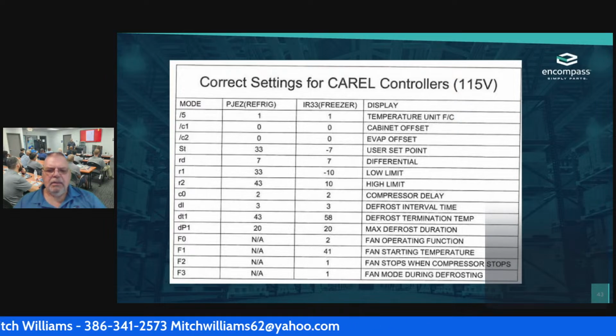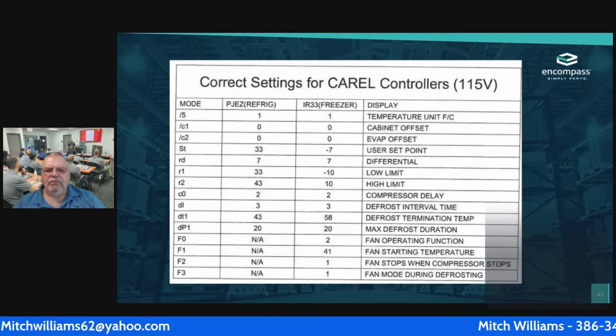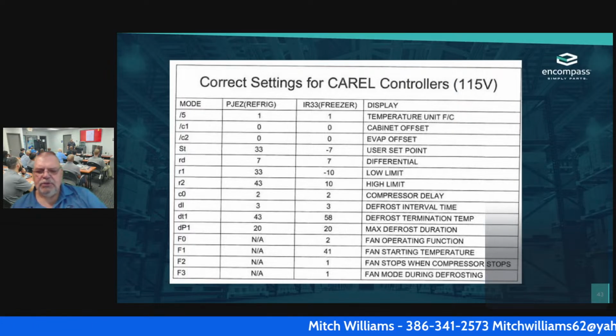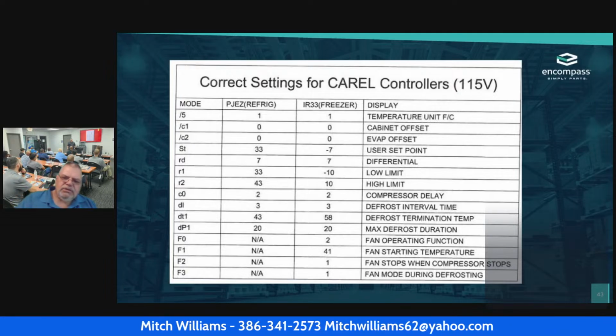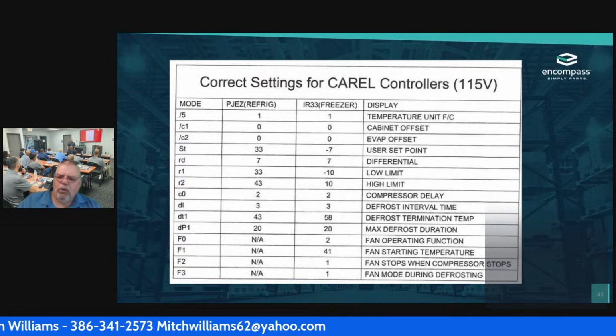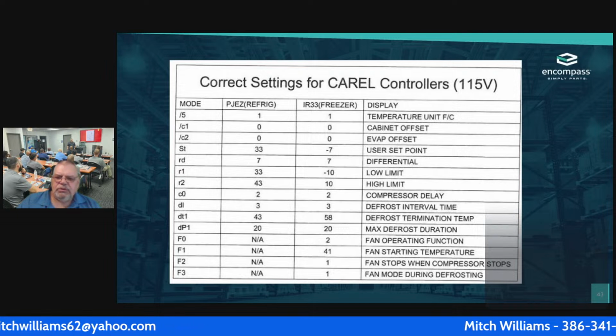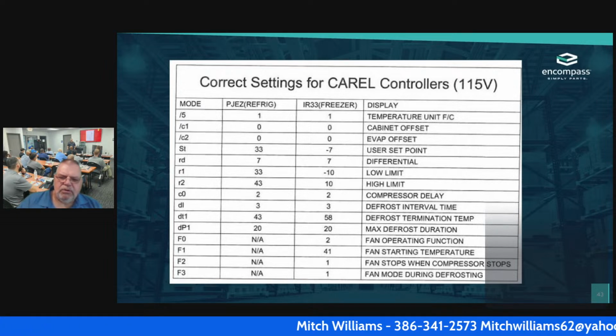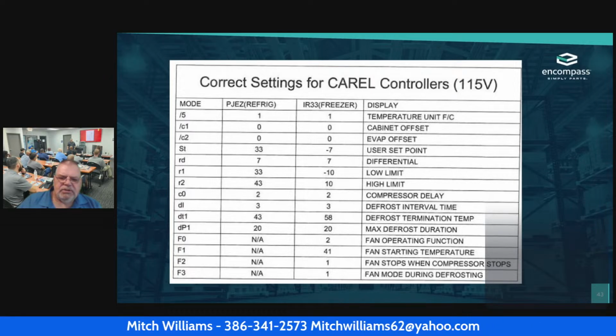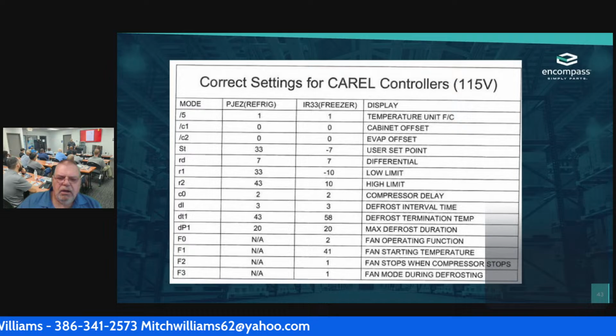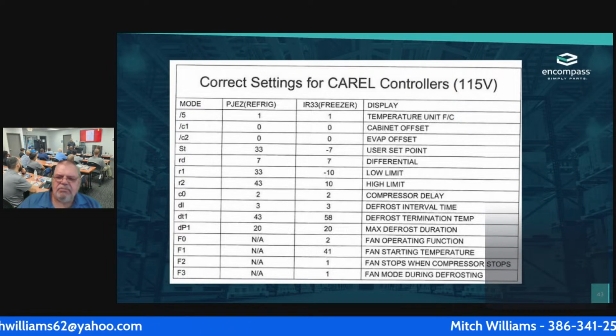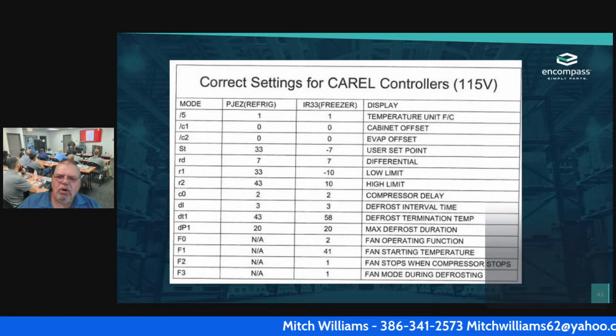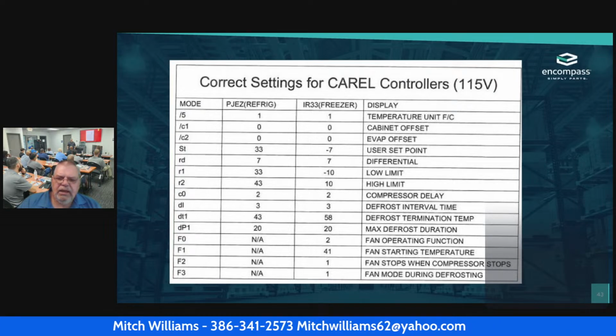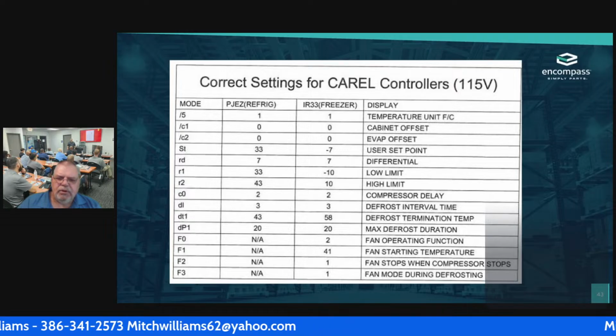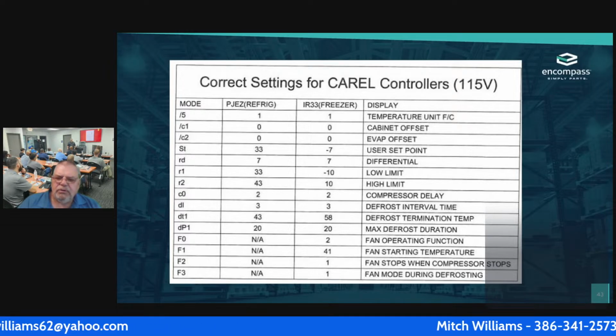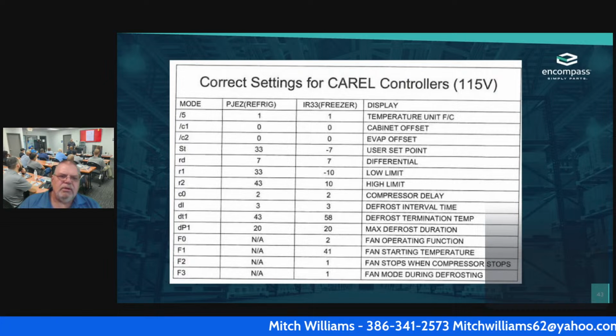That's the fan operating. Then F1, it's not applicable for the fridge. And for the freezer, it's set at 41. That's the fan starting temperature. So once this unit reaches 41 degrees, the fan will start. If it's below that, it's still going to start. If it goes above, that's going to be my problem. So F2, of course, the refrigerator is NA, and that's the stop when the compressor stops. It's set for 1 on the freezer. And then F3, same thing for refrigerator. It's not applicable. And then the freezer is the fan mode during the defrost cycle.